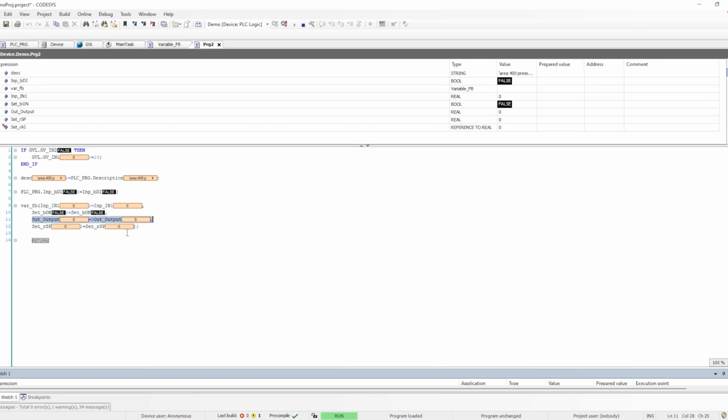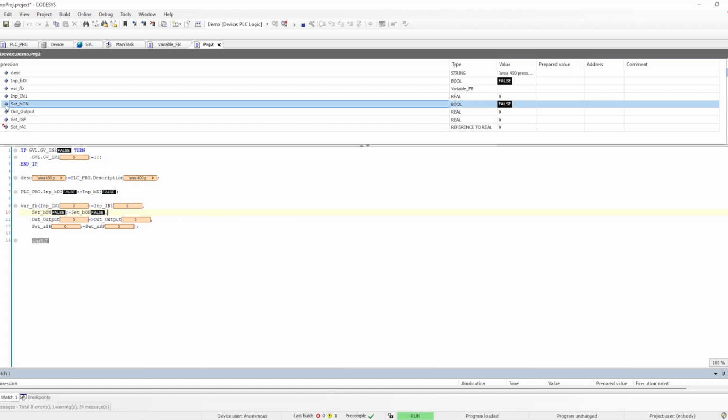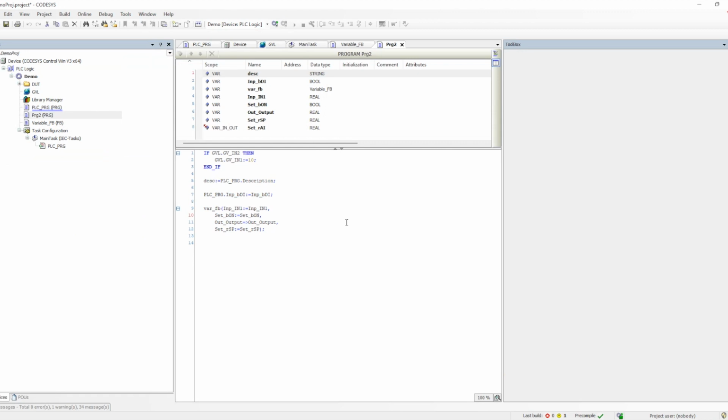Why is it happening? Because these are getting written from the outside, correct? So these are the VAR_INPUT, and those input variables are not retained. When we start the PLC, these variables are getting written from the outside, so the value was not initialized with anything. That's why those parameters don't get retained. Only the status, because that is local and it is scoped inside the function block only.